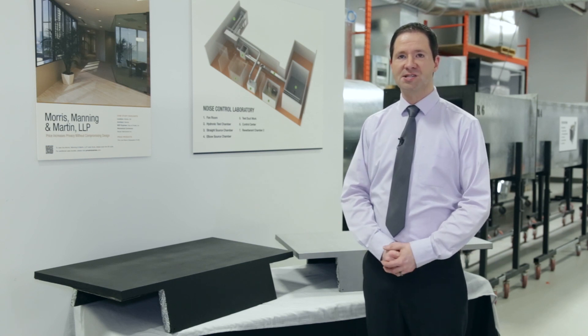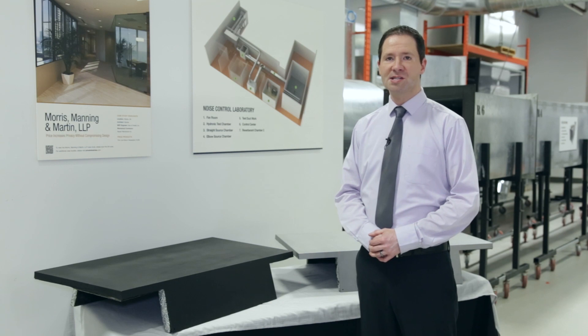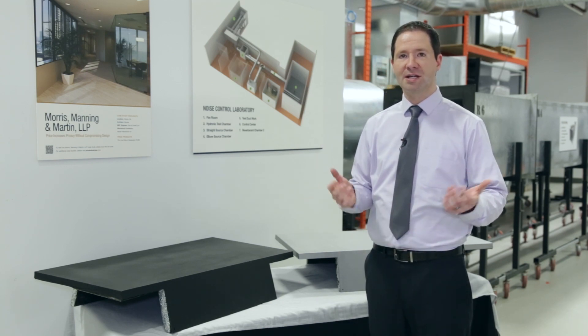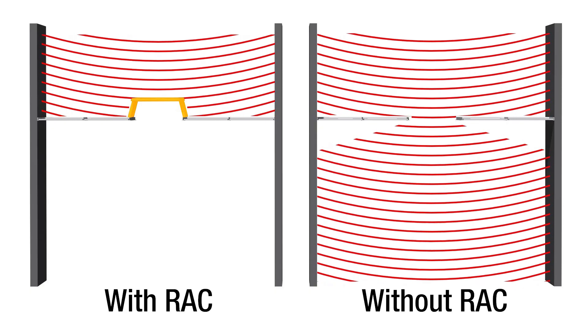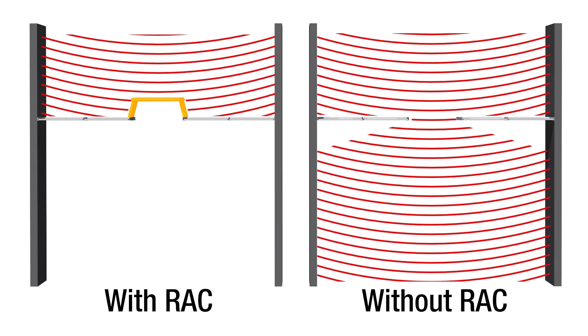The third advantage is that it has high performing transmission loss performance. This is great because it no longer has the return air opening as a weak link acoustically within a system. The opening within the return air grille will ensure transmission loss to the surrounding acoustical tile ceiling. It also has the direct advantage of blocking the complete line of sight into a return air plenum, no longer being able to see mechanical equipment through a return air opening or having light transfer between these openings.